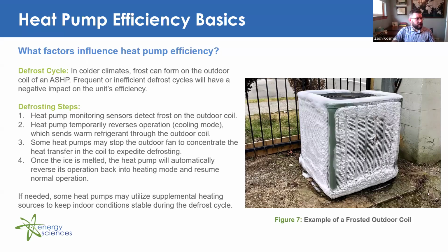So I'll go through the defrosting steps quickly. First, your heat pump has sensors that monitor and detect the frost on the outdoor coil. The heat pump will temporarily reverse operation. In other words, it'll transfer into cooling mode, and it'll send warm refrigerant through that outdoor coil to start melting the frost. Some heat pumps may stop the outdoor fan to concentrate the heat transfer in the coil to expedite defrosting. And once that ice is melted, the heat pump will automatically reverse its operation back into heating mode and resume normal operation. If needed, some heat pumps may utilize supplemental heating, i.e. a boiler or a furnace, to keep the indoor conditions stable during that defrost cycle.